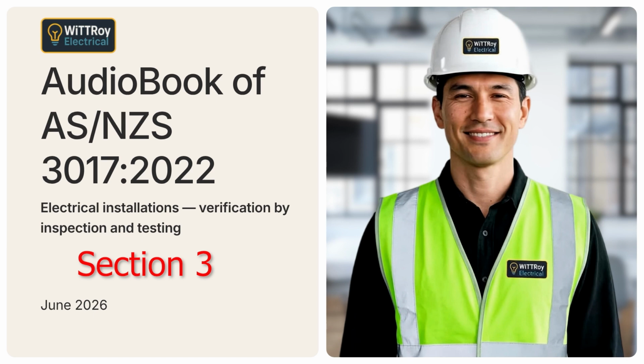In simple terms, a switchboard inspection asks, is it in the right place, safely accessible, correctly built, correctly labelled, correctly protected, and correctly connected? For wiring systems, conductor size must be checked in relation to the protective devices. In simple terms, the cable size and protective device must work together. The cable cores must be identified correctly. The wiring must have adequate support and fixing. Connections and enclosures must be checked.